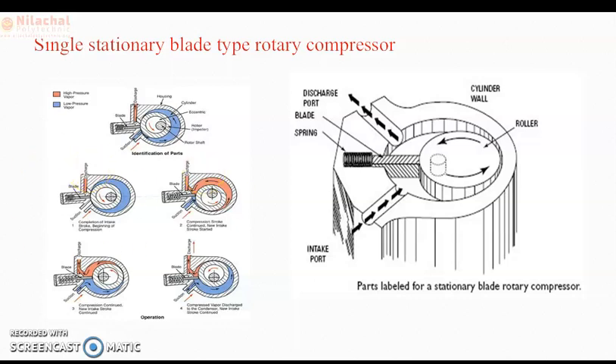As the roller runs towards the middle position, the second figure shows the roller in the middle position. In the third figure, more vapor refrigerant is drawn into the cylinder while the compressed refrigerant is discharged to the condenser. At the end of the compression stroke — shown in the fourth figure — most of the compressed vapor refrigerant is passed through the discharge port to the condenser, and a new charge of refrigerant is taken into the cylinder.